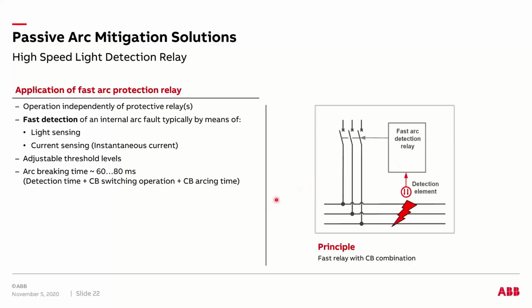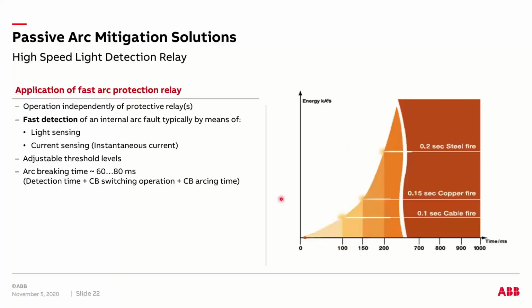as well as you can use the other high-speed output contact to trip your tiebreaker, right? But one thing to keep in mind is the breaker operating time, right? So if it's a medium voltage switchgear, and if you have typically like a 3-cycle or a 5-cycle breaker, considering a 5-cycle breaker for the worst case scenario, it could be anywhere from 75 to 80 milliseconds until you completely interrupt an arc flash event within your equipment, right? So there is a possibility of an arc flash that keeps developing within your equipment for about 80 milliseconds.